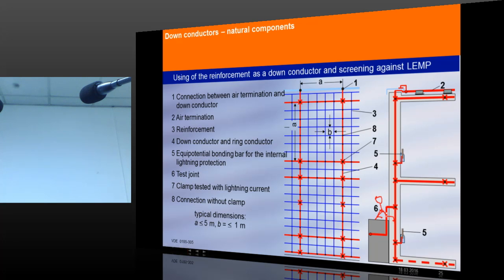So, in this particular case, you imagine a building which is very close to the main road. That means you cannot extend and you cannot place a ring conductor on the road because the authorities will not allow you. In that case, this particular steel foundation is enough to dissipate the lightning current. Again, under some condition. One of the conditions is, in most of the high-rise buildings, the parking area is underground. Level 1, level 2, level 3, level 5, and sometimes even up to 8 levels under the floor.